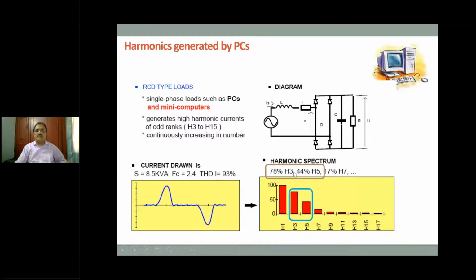When you split it into 3, 5, 7, and so on, you will find that out of 93, 78 is third order, 44 is fifth order, 17 is seventh order, and so on. So all orders of harmonics are harmful to your grid, to your network system. And these are caused because of the rectifier circuits. So this is the problem with harmonics. Your PC, whatever you see at home, electrical gadgets like your TV, they are all causing heavy harmonics to the network.